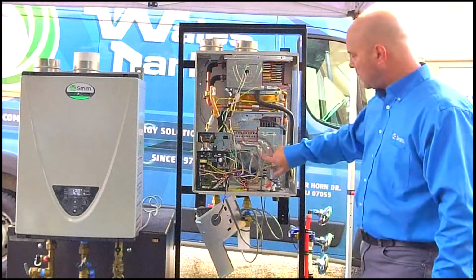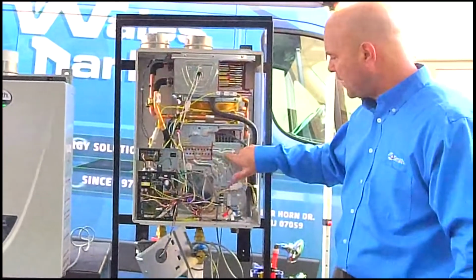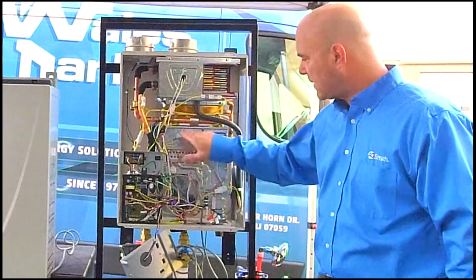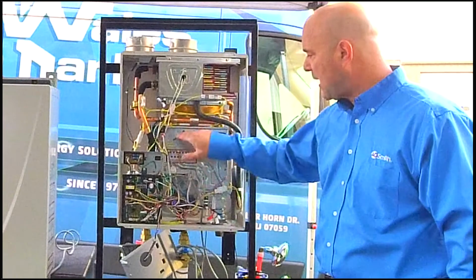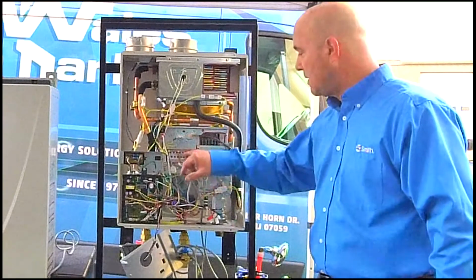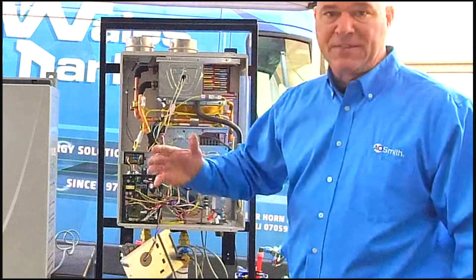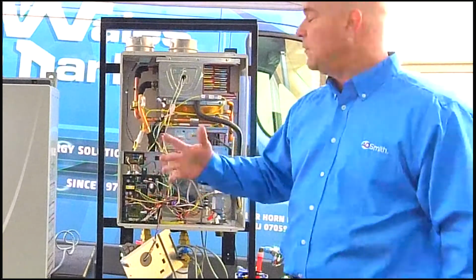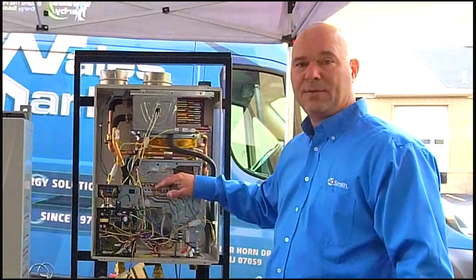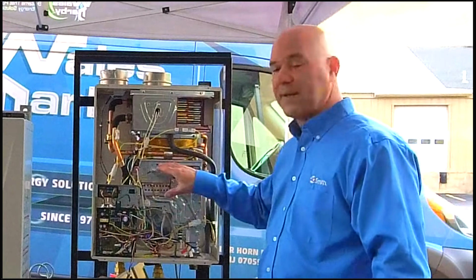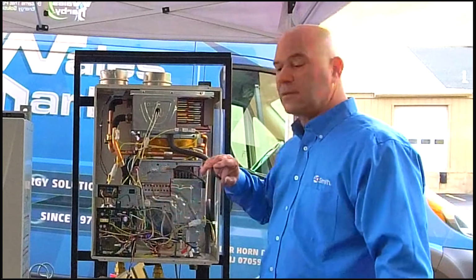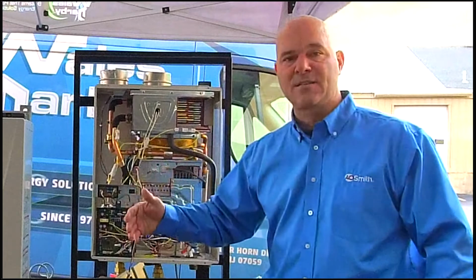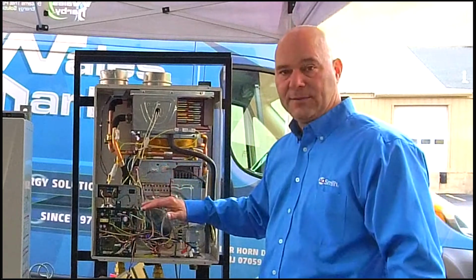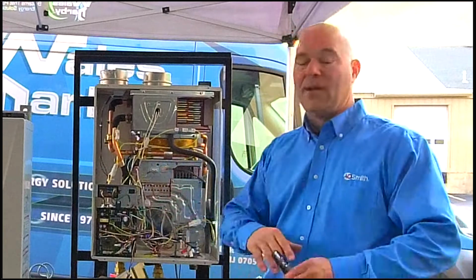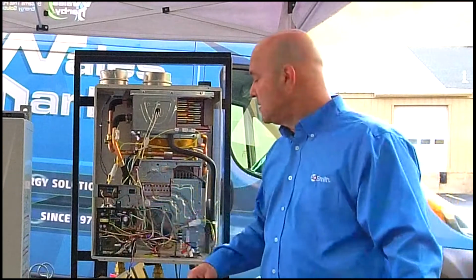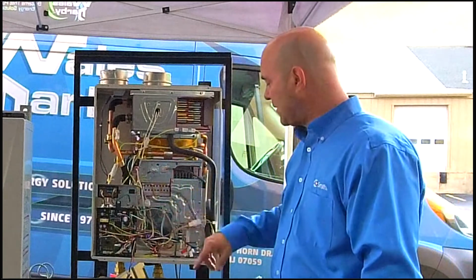This is a cutaway. There are 3 gas tracks, 1, 2, 3. The center one right here, directly below the igniter and the flame rod, that's the one that will be running the most. A.O. Smith does something a little bit different here. When we see a demand of water, we automatically fire to maximum input. So this unit, 199, we're going to fire to 199, and we're going to get the water up to your target temperature as fast as possible. Then we'll back it down to marry up to whatever the demand is. So 1, 2, 3 tracks.